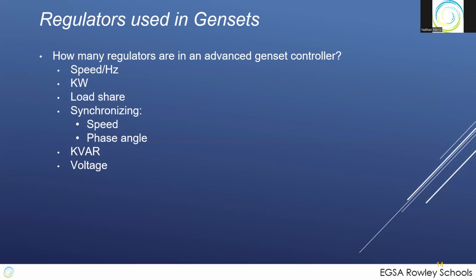Synchronizing regulators are also needed. As you synchronize a gen to a gen or a gen to utility, you have to bring your speed up close. Then once you get your speed within a few percent, maybe half a cycle or so, you'll turn on a phase angle regulator. You'll actually look at the phase angle difference between the generator and the source you're syncing to.